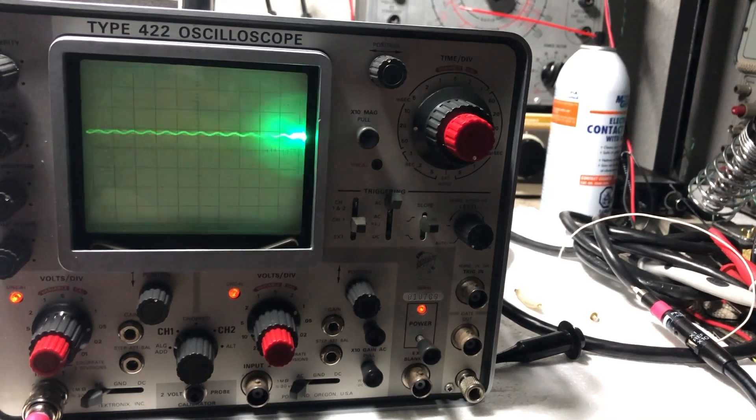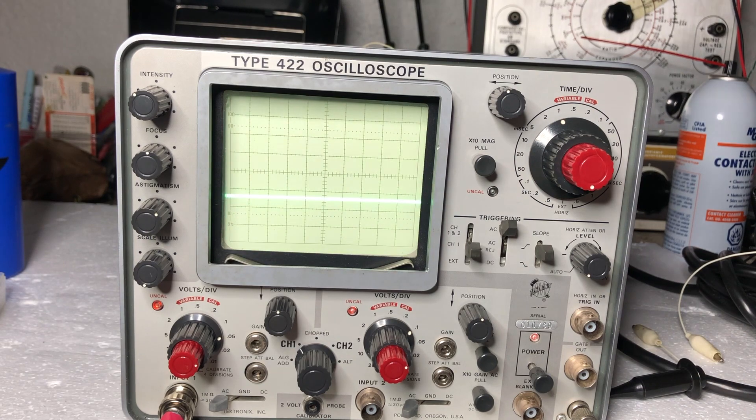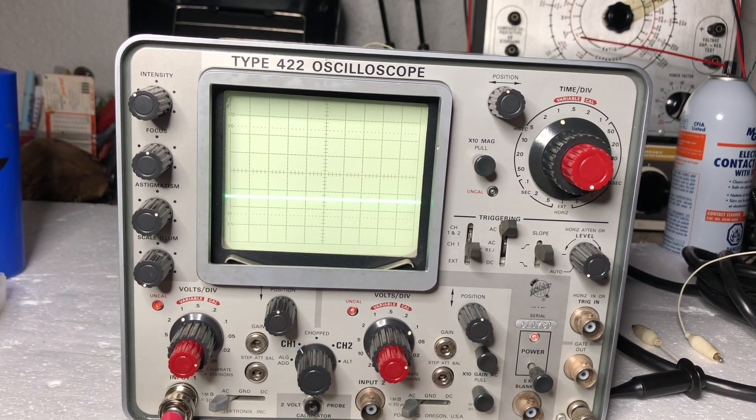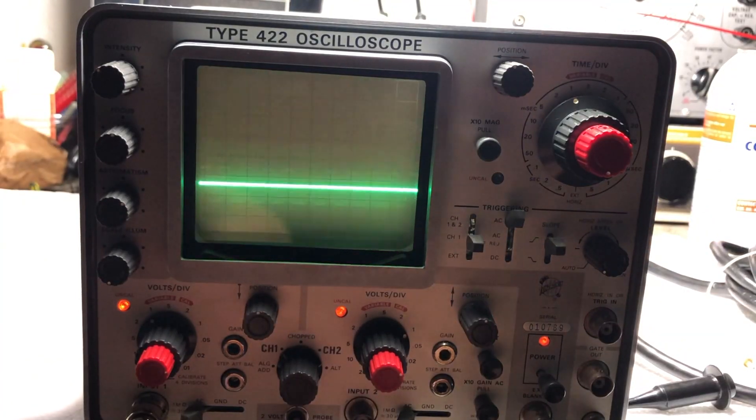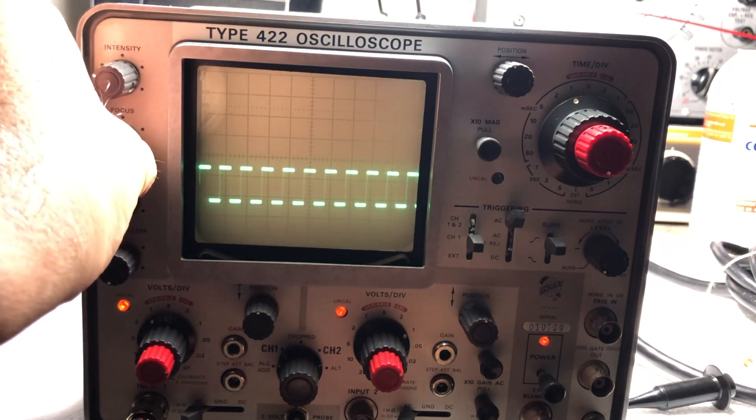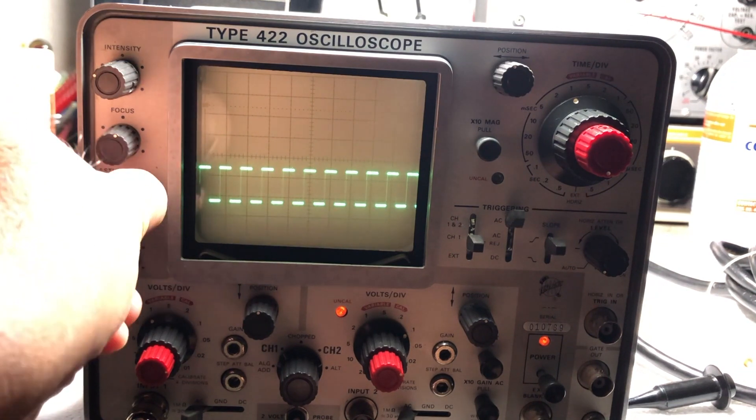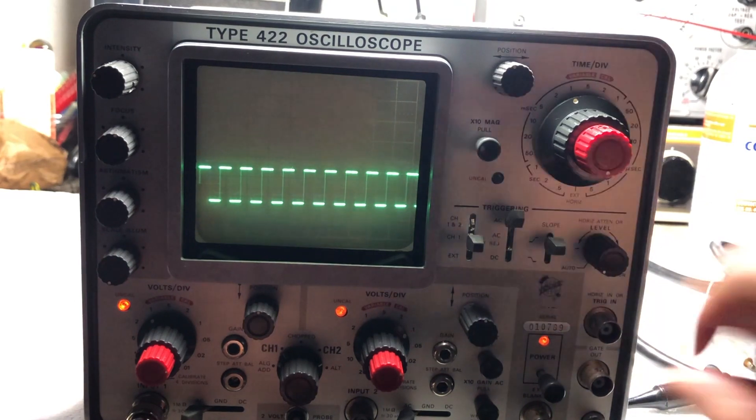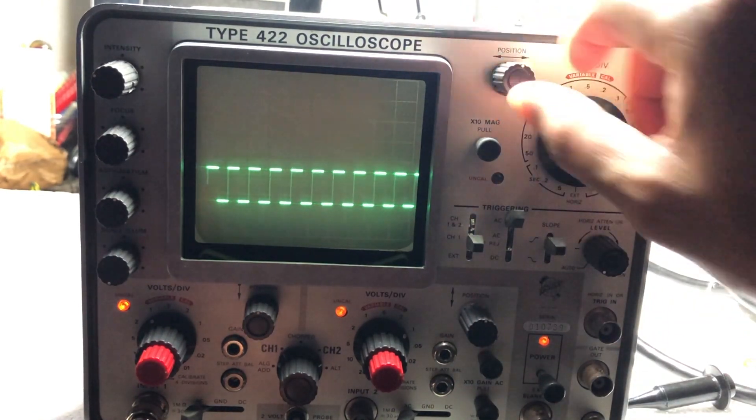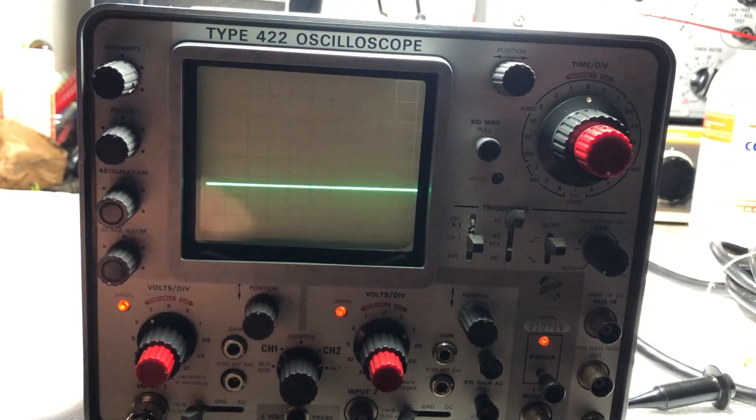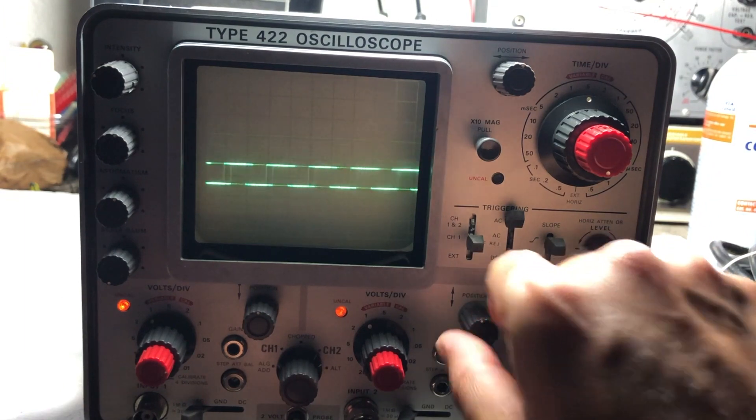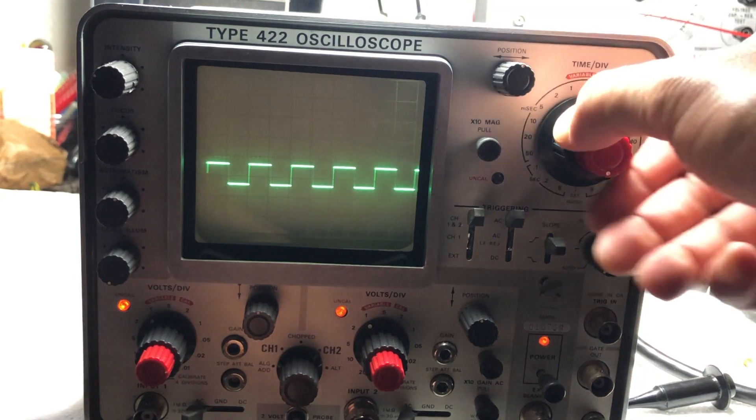Okay, here you go. It's all done. It's up and running. I've connected a probe. Let me put the two volt calibrator signal. Happy with the CRT—pretty sharp focus and intensity. Done. Let me try the other channel. That's about it.